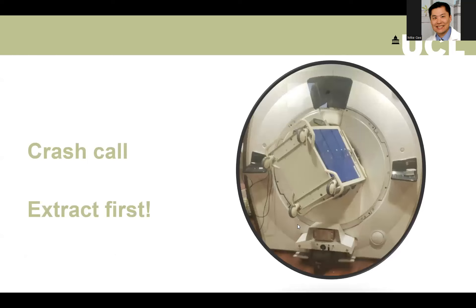If there is a crash call, do not push the crash trolley into the scanner room — the trolley and its contents are never MR compatible. Get the patient out to a safe environment first. Make them safe in a different environment before the crash team can intervene. Even if they're having a contrast reaction, stop the scanner, get them out, and then involve the crash team. Do not quench.